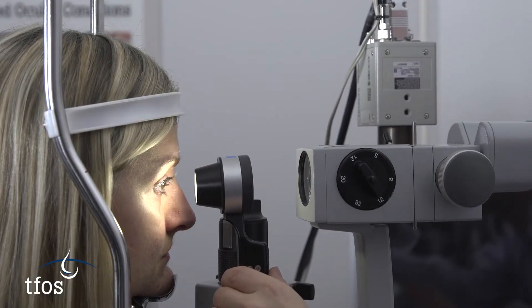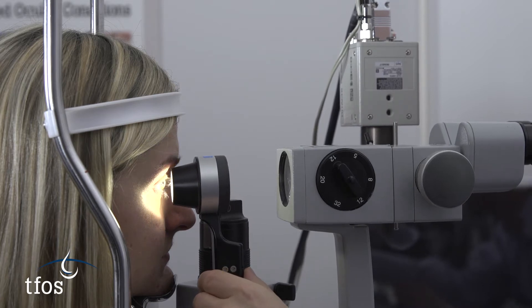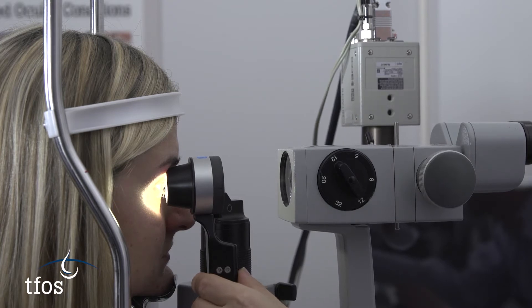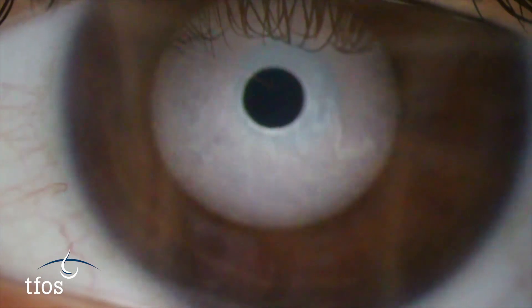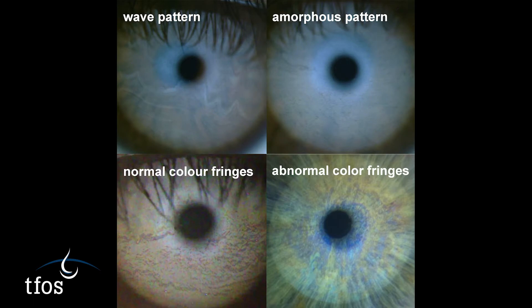Some clinical tear film imaging instruments have been designed for use in combination with the slit lamp to provide magnification to highlight the lipid layer. Visualisation of the lipid pattern is facilitated by the instrument's wide-field cold white light illumination. Lipid layer thickness can be estimated from the patterns visible, which range from thinner meshwork patterns through wave or flow patterns and amorphous patterns to coloured fringe patterns.